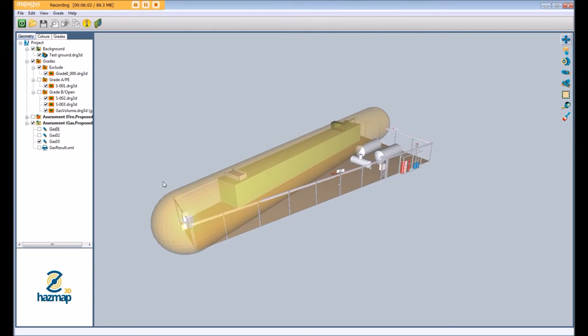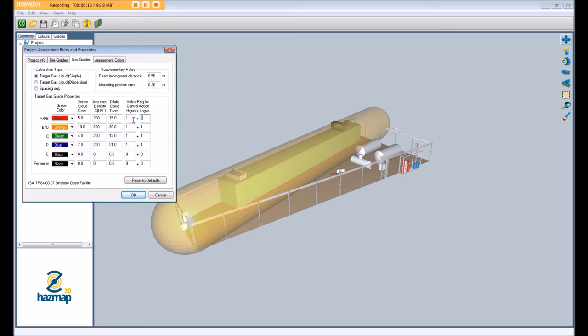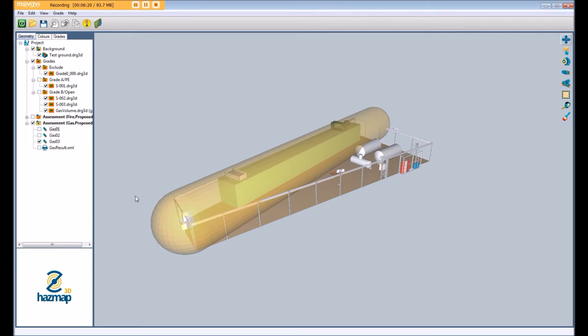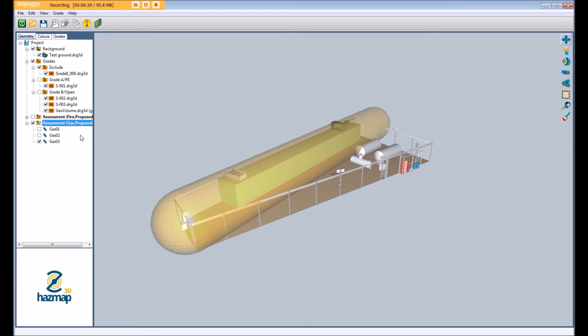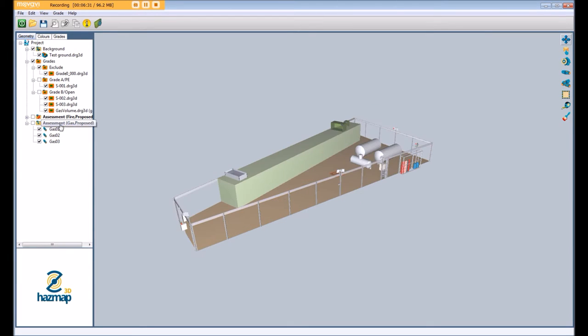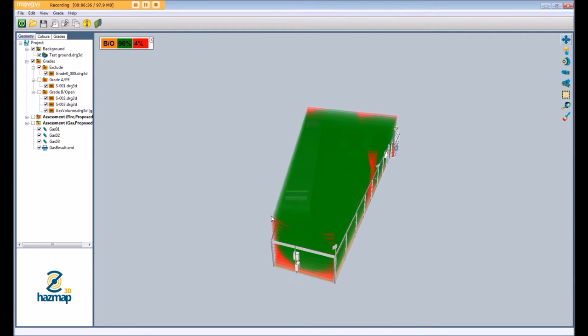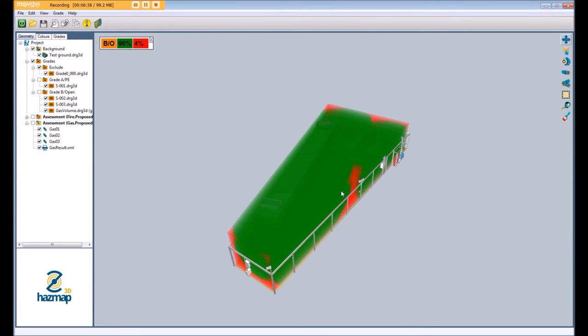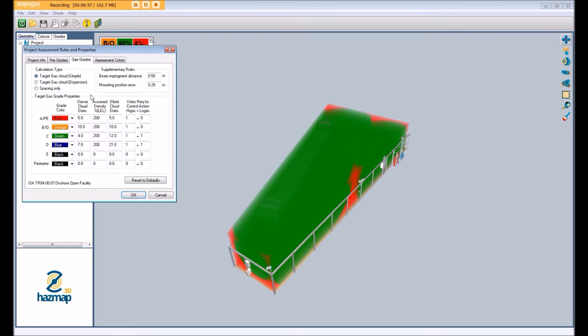To review what this means from a methodology standpoint, when we go into our grades table here if we were simply using target gas cloud we would simply exclude the fact that there's any dilution of that cloud and we would simply make it a 1 out of n coverage. So if we have a look at this now and obviously make our dilute cloud the same as our dense cloud, change the voting to 1 out of n, when we run this assessment you'll see what's typically shown as the simple coverage model. So any single point that's within 10 meters of the open path or the point gas detector is shown as covered. Obviously in reality that's incorrect, or at best a misrepresentation of how those detectors actually operate in the field. This is really referring to the beam attenuation model that's within HazMap 3D which is absolutely crucial in representing open path gas detectors in the way that they typically are applied.